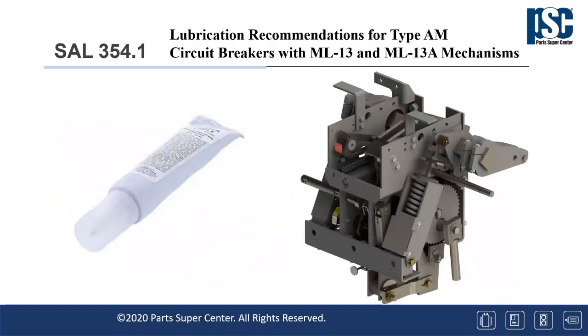Next is SAL 354.1. This is for changes to the recommended greases for the Magneblast breaker and switchgear. A superior red synthetic hydrocarbon grease now replaces the white or amber mechanical grease and the black contact grease for periodic maintenance and general overhaul. This new recommended grease was successfully design tested and qualified during continuous current tests, 10,000 operation design life tests, as well as short circuit power testing. The change to this grease is effective 1990.